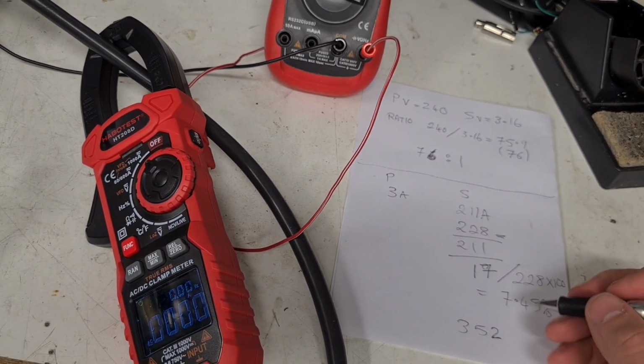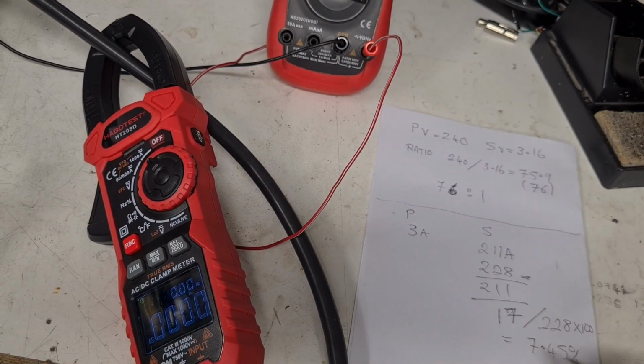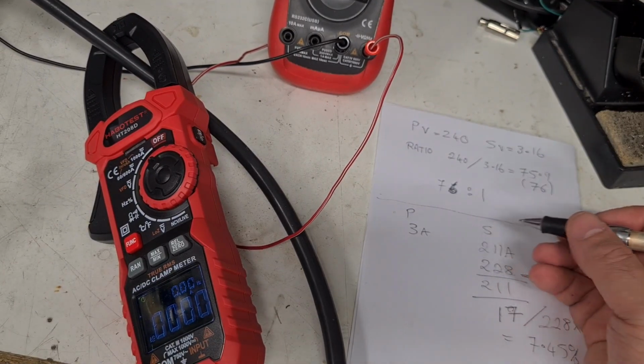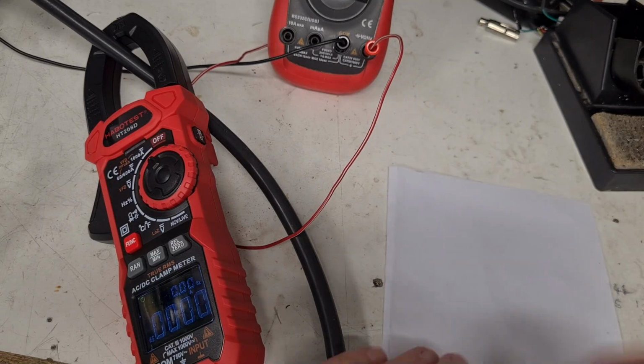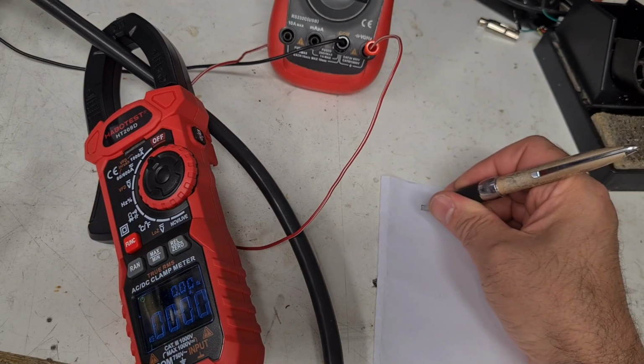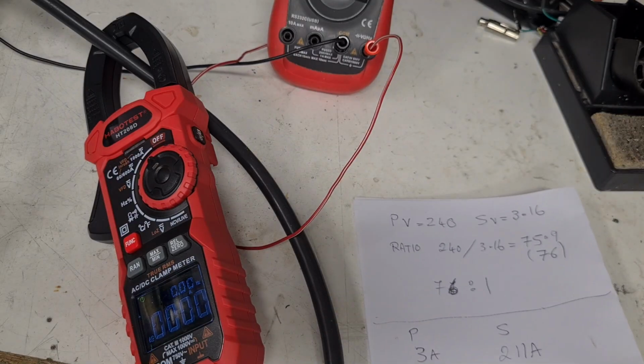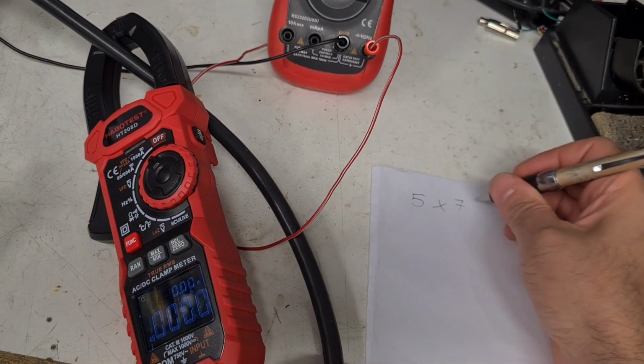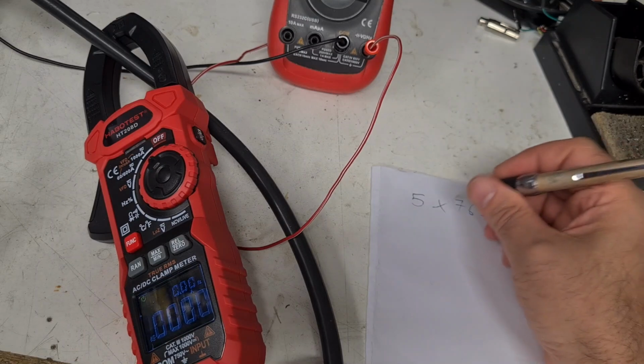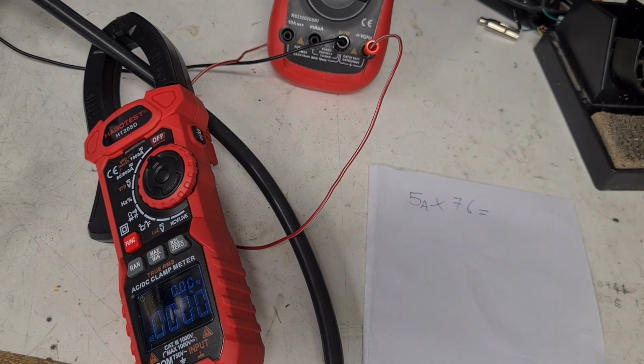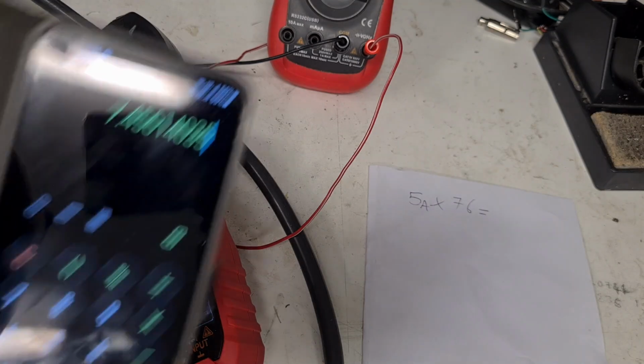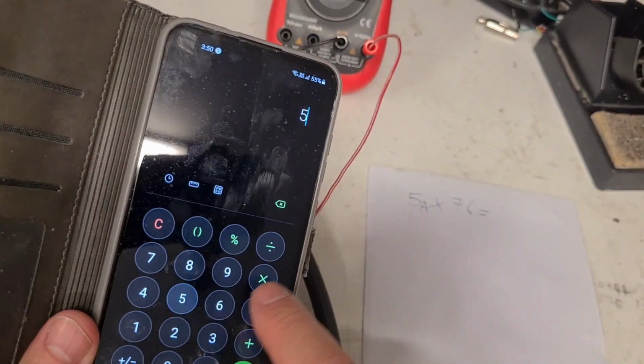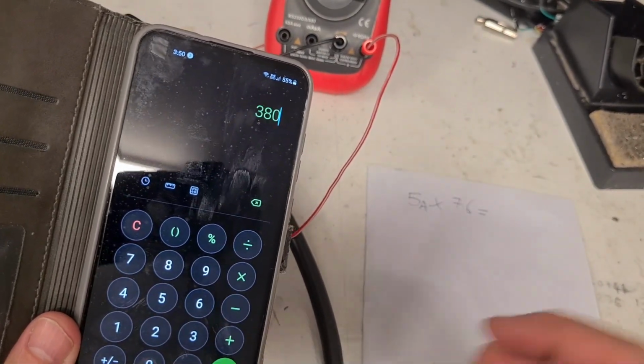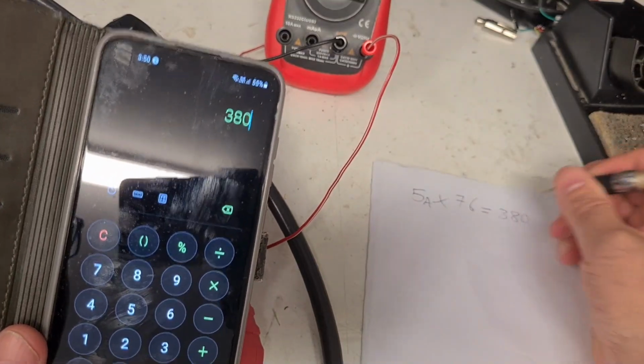Now, so before I had 7.45%. Now let's see. Let's do this calculation again. So 5 amps times 76, I said we're going to work. The ratio equals, that's amps, how much the secondary should be without any losses. Okay. So 5 times 76, 380. That's what we should have read, 380 amps.